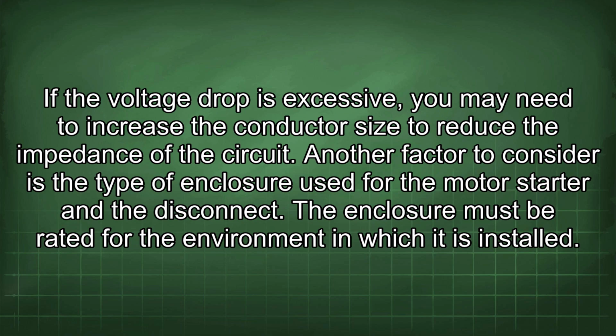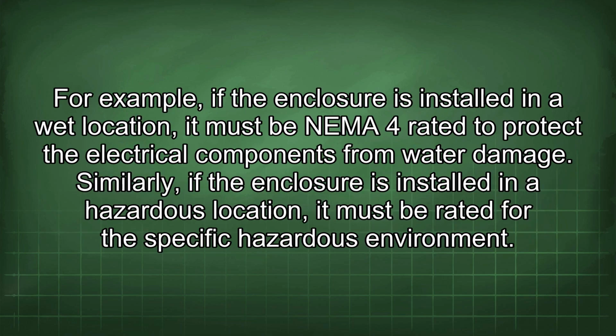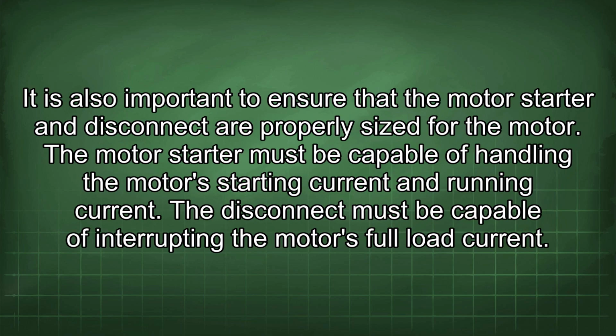circuit. Another factor to consider is the type of enclosure used for the motor starter and the disconnect. The enclosure must be rated for the environment in which it is installed. For example, if the enclosure is installed in a wet location, it must be NEMA 4 rated to protect the electrical components from water damage. Similarly, if the enclosure is installed in a hazardous location, it must be rated for the specific hazardous environment. It is also important to ensure that the motor starter and disconnect are properly sized for the motor. The motor starter must be capable of handling the motor's starting current and running current. The disconnect must be capable of interrupting the motor's full load current.